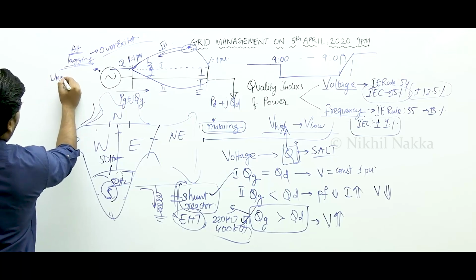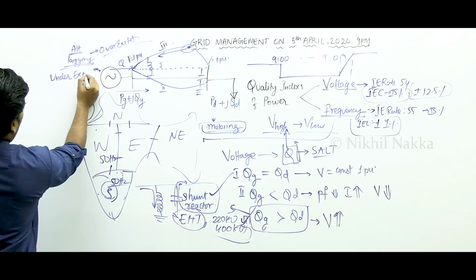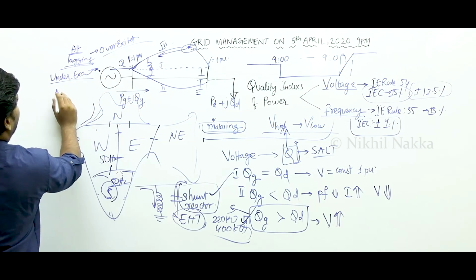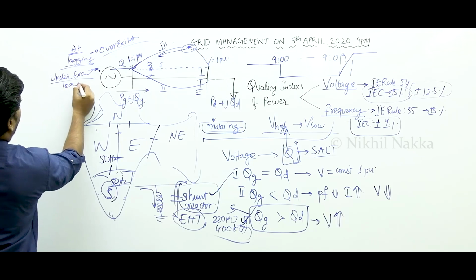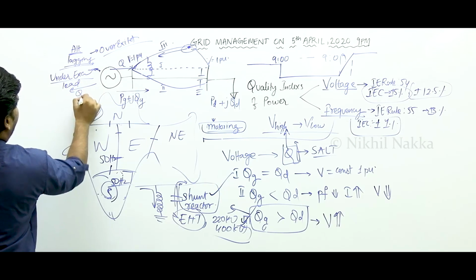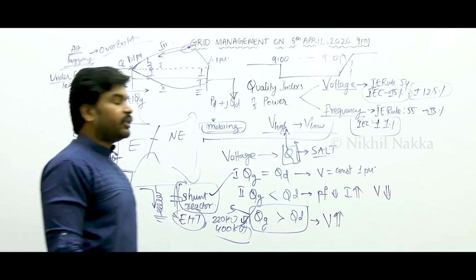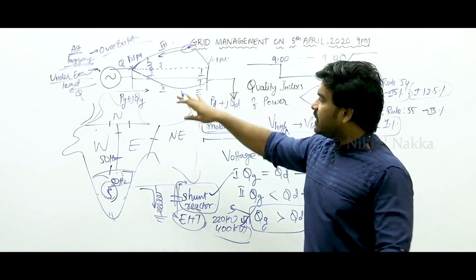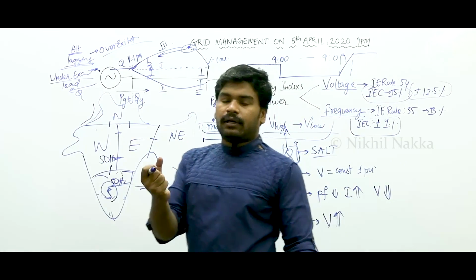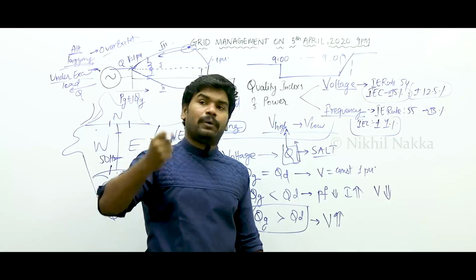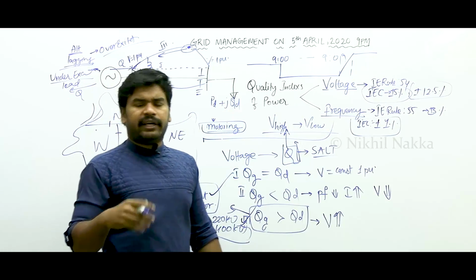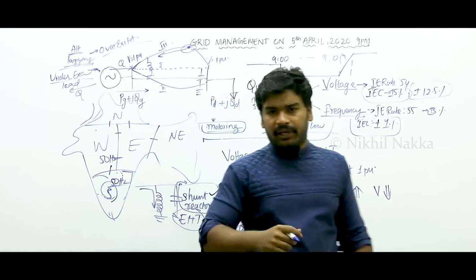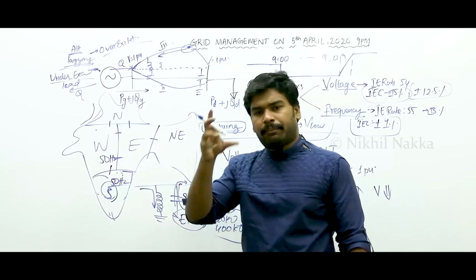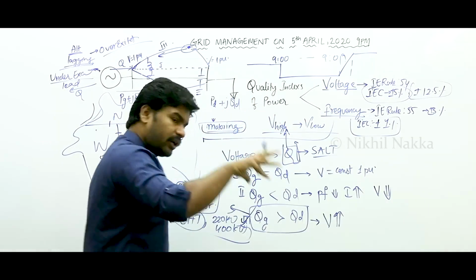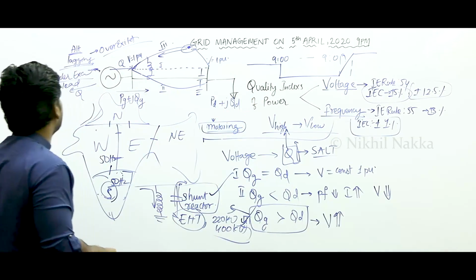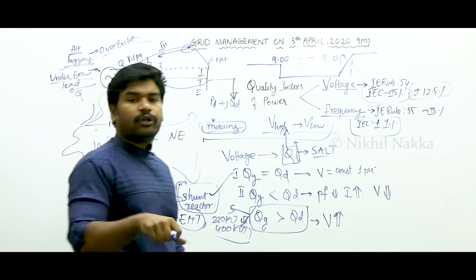But when you are under-exciting it, when you are going to under-excite this synchronous machine, the alternator, it will go into leading power factor and it will absorb the Q. It will start absorbing the Q. So every generator has got a limited constraint of how much reactive power it can accept. That is determined by something called the capability curves of that particular generator. It will be provided by the manufacturer only. So according to what the capability curves of the generator say, that much reactive power they will try to absorb.